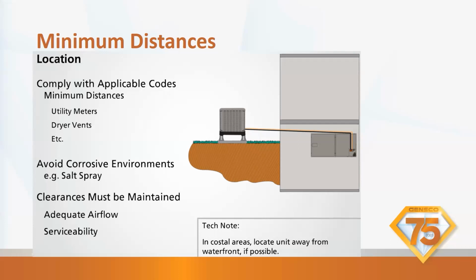There is a piece of plastic, looks like visqueen, inside of the units that covers up the reversing valve and the TXV and all that stuff on the outdoor units. That is in there on purpose to keep the salt spray off of those components. If you pull that out and you're near the waterfront, you could have a lot of deterioration from that. That's why that's in there. So don't take it out if you live in that kind of an area. Now, if you live in Montana, places like that where we don't really have humidity, Idaho, where I live, we don't really have a lot of humidity. We don't have any salt in our air. So you can take that out. But in a coastal area, make sure that you leave it there.